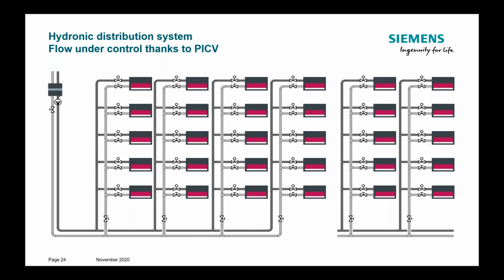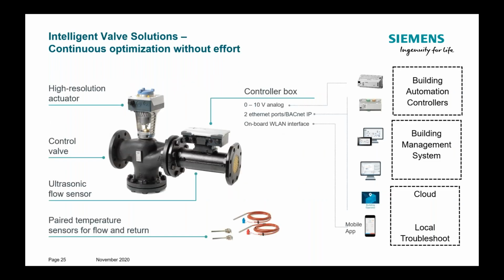And what would we need for this? We would need more information from the system. We would need local temperatures of flow and return to the risers and to the consumers. We would need power measurement to the risers so that we can react on the power consumption of each and any of these risers. And we need it online on the BMS system, to have it under control and also to supervise the system. So a PICV could not do this from today's perspective. Let's have a look at a solution which can do such things.